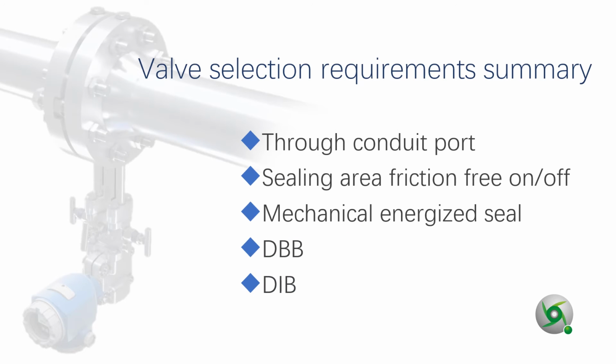To summarize all above, the following features are musts for metering valve application. They are through conduit port, sealing area friction-free on-off, mechanically energized seal, DBB, and DIB.